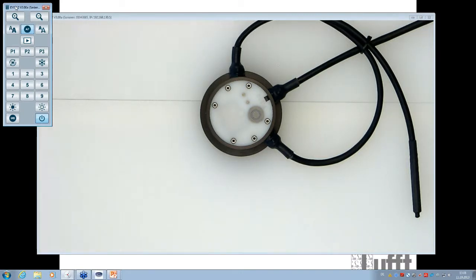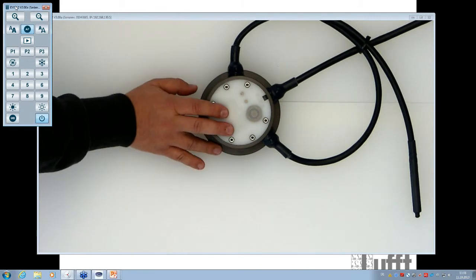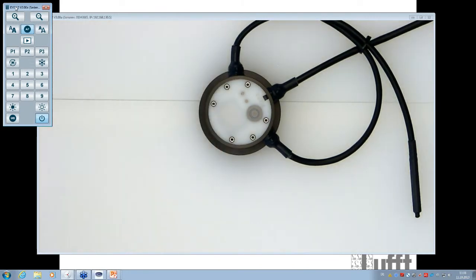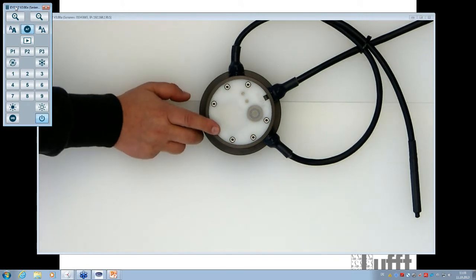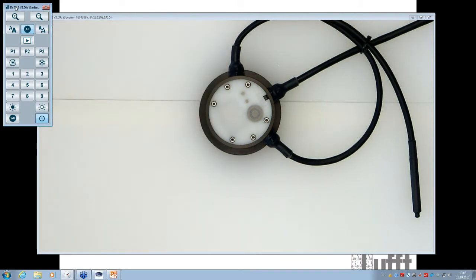This sensor is adjusted at 0 degrees for the freezing point. That means the optimal outside temperature is 0 degrees to get the best performance here. So if you want to do the calibration outside in the summertime, for example at 25 degrees, this measurement will not be very accurate, right? So you have to know that. The best day for such a calibration will be a day with 0 up to 5 degrees Celsius outside temperature.